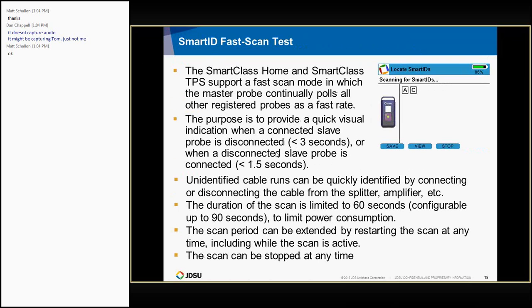Okay, the fast scan test, I think I've already described it in some detail, but this is only on the SmartClass Home and the TPS. The DSAM I don't think is using this feature, but it provides a quick visual indication when probes are disconnected. It should show them drop out of the list in less than 3 seconds. When you connect a disconnected probe, it happens quicker than that, within a second and a half or so.